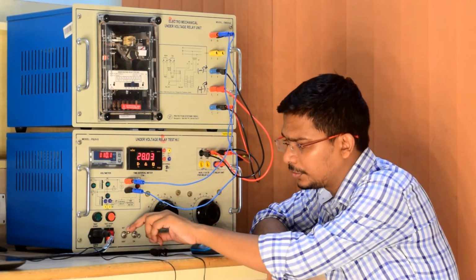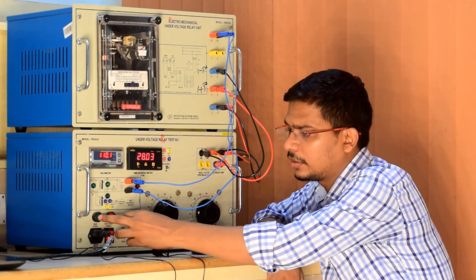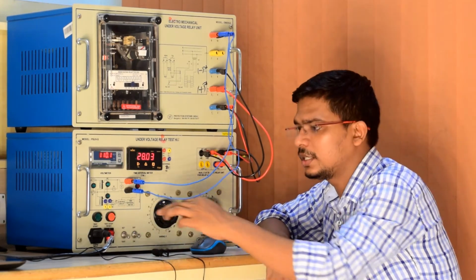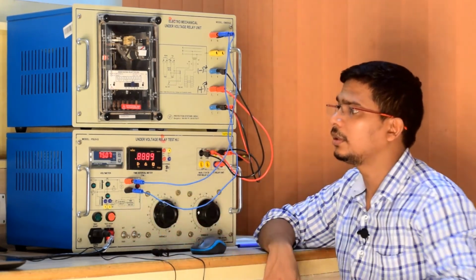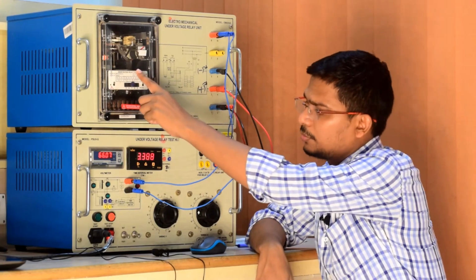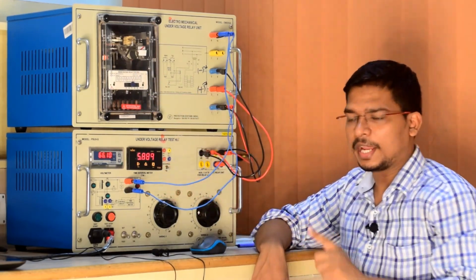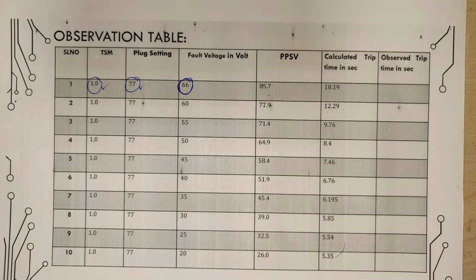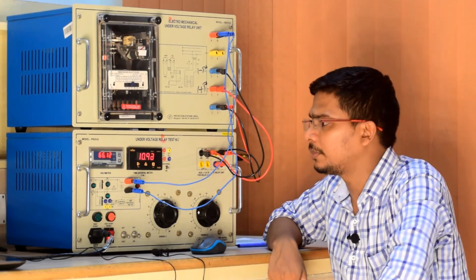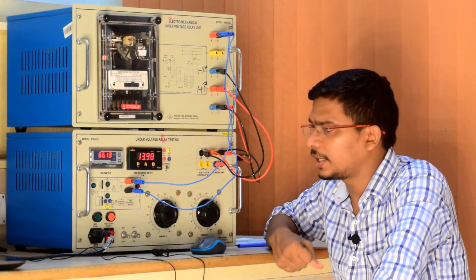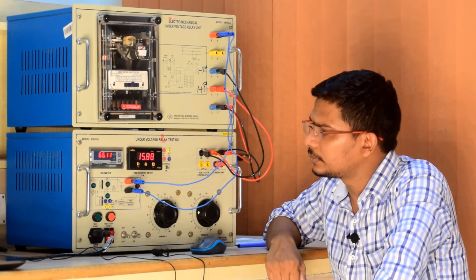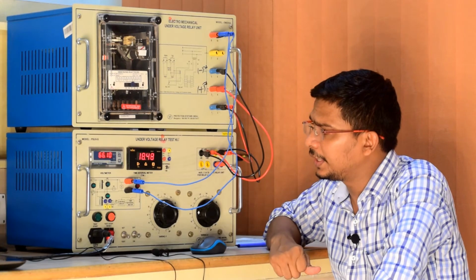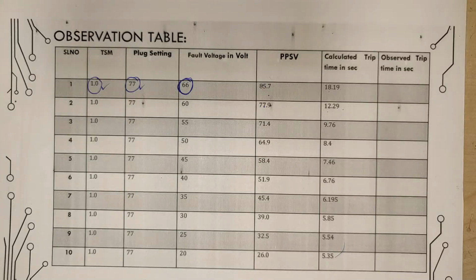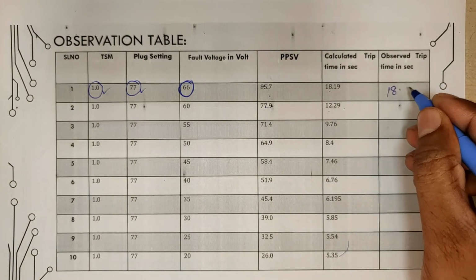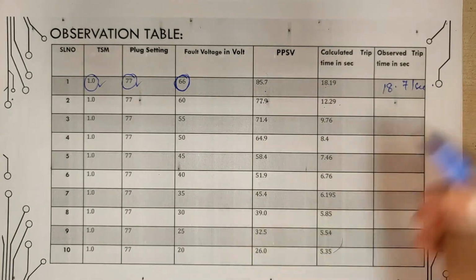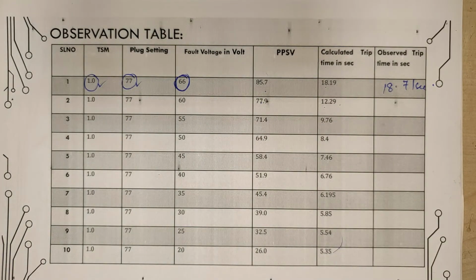Then we have to put to test mode, then turn on the circuit breaker. Already you have set 66, so directly that voltage will apply to the relay, and you can see the relay disc is moving. After the set time, our approximate trip time is 18.19 seconds, so near to that it will trip. We have to wait for almost 18 seconds. 16, 17, 18, 18.71, exactly what we were expecting. So that is 18.71 seconds.